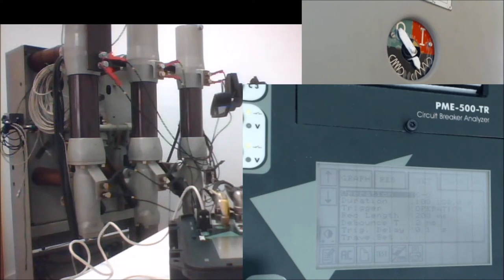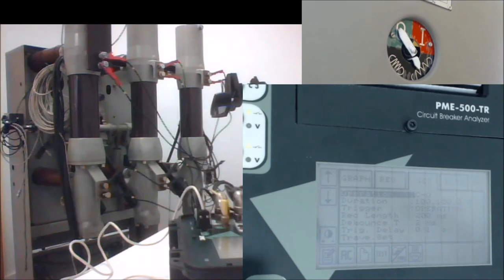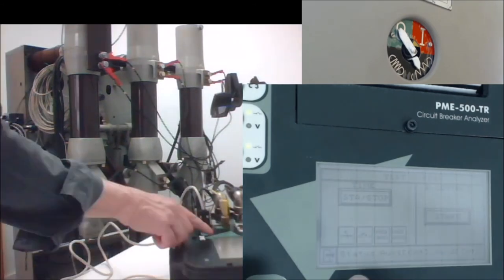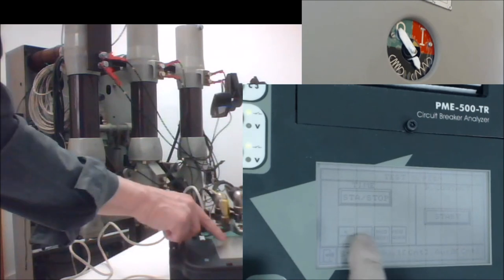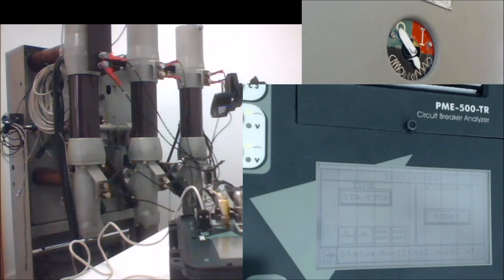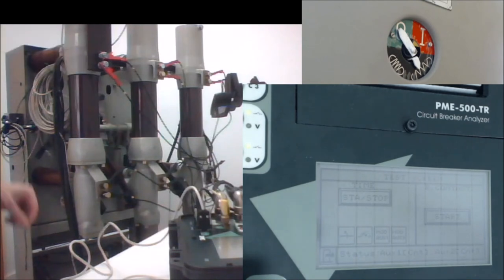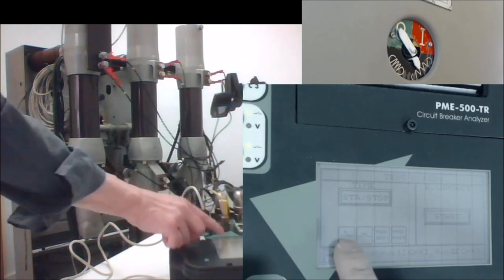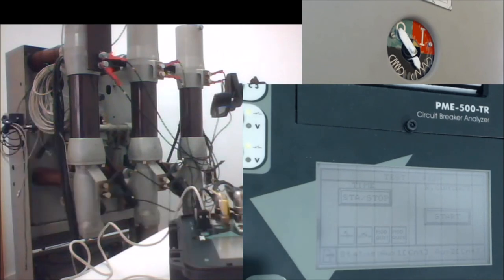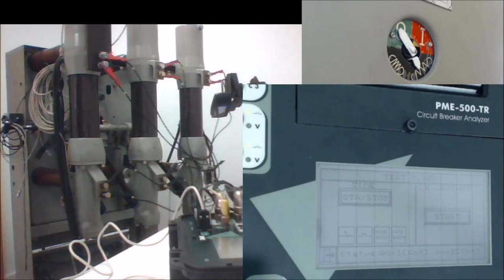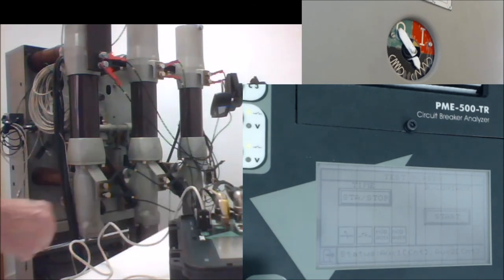Let's start with a simple close-open test. We exit from the settings by going directly to the test screen. In the test screen there are buttons that allow you to operate the circuit breaker manually. This is very useful to check that your control connections are correct — that you are connecting the instrument properly to the operation coil in the circuit breaker. If you have any errors, these manual buttons will not operate.